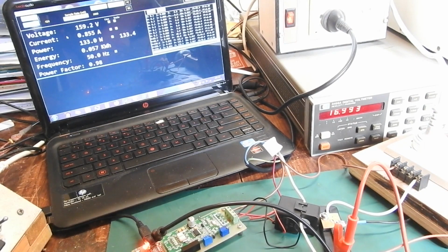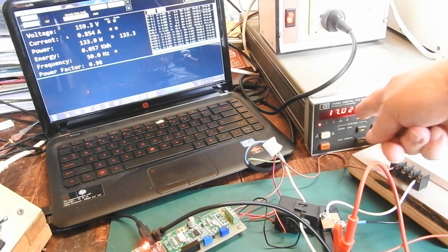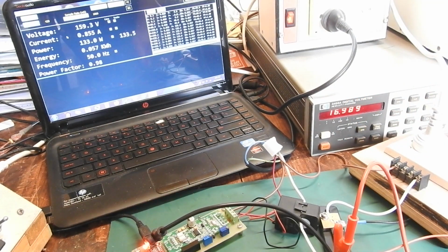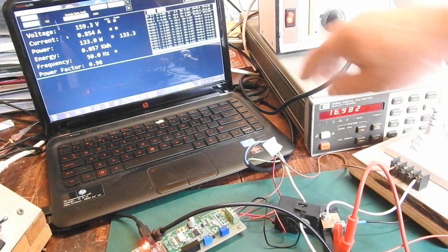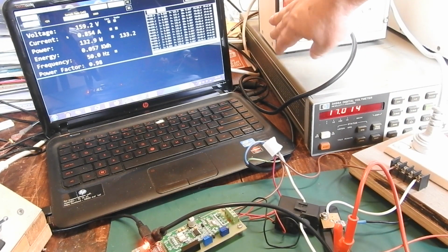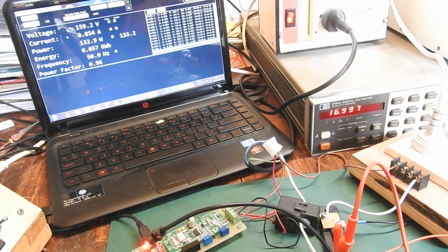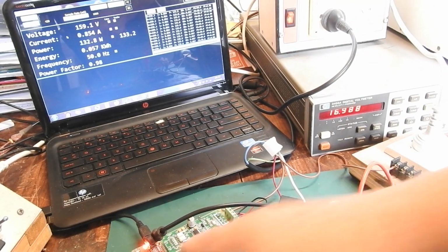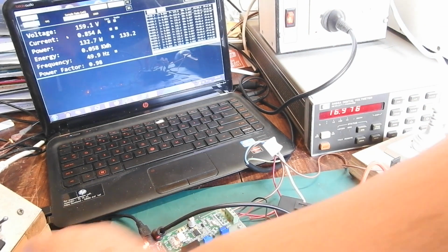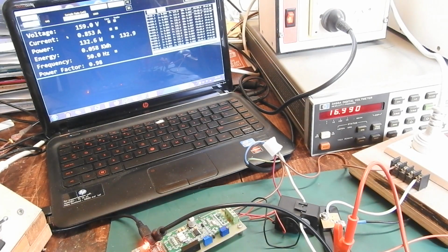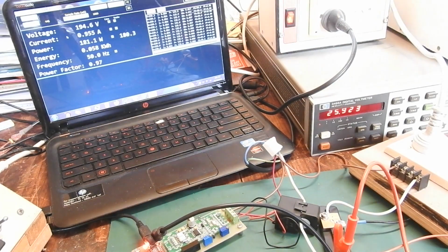We're back to measuring AC volts, and I'm doing it between the active — it's not really active because of the floating due to the isolation transformer — but the voltage difference between that and the earth terminal on the low voltage side, and winding it up to full voltage, we're seeing 26 volts.